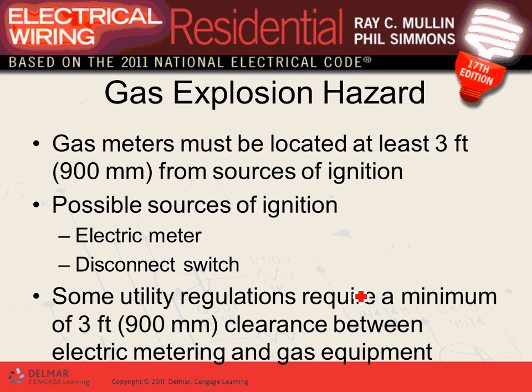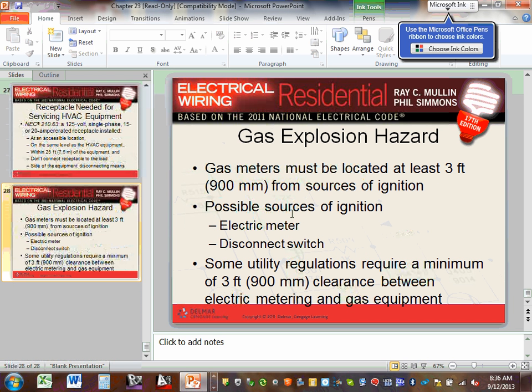When locating gas meters and electrical equipment, you need at least 3 feet of separation between the gas meter and any ignition source such as the electrical meter, disconnect switches, or other electrical equipment. Placing a gas meter next to an ignition source creates an explosion risk.